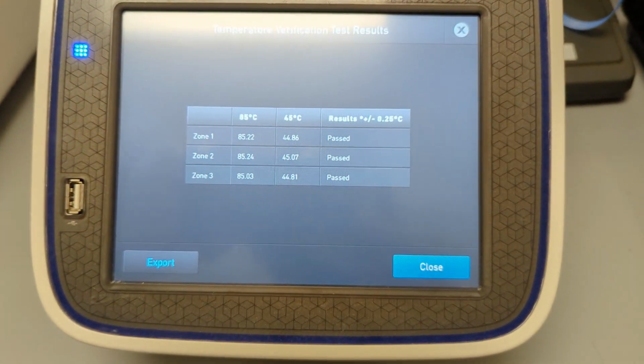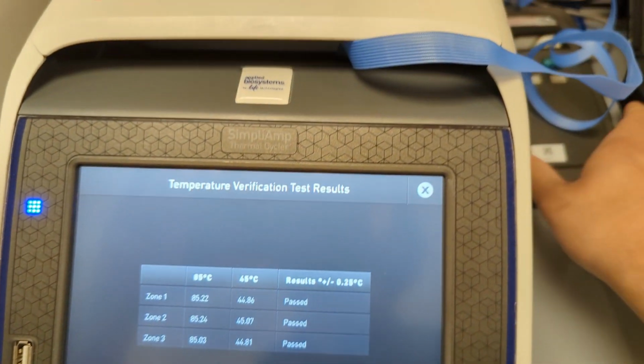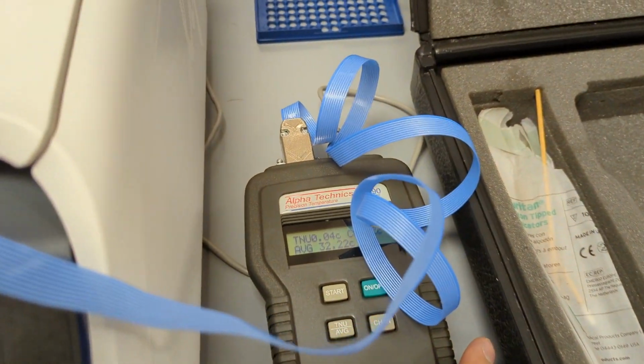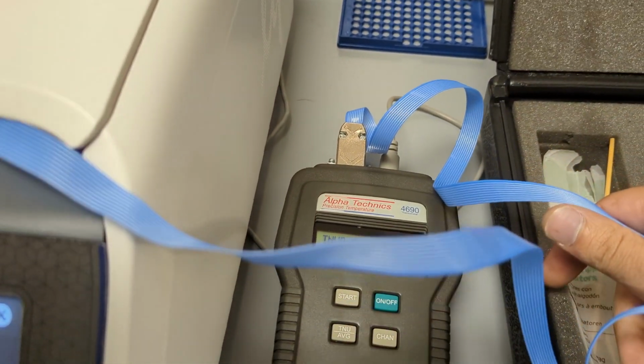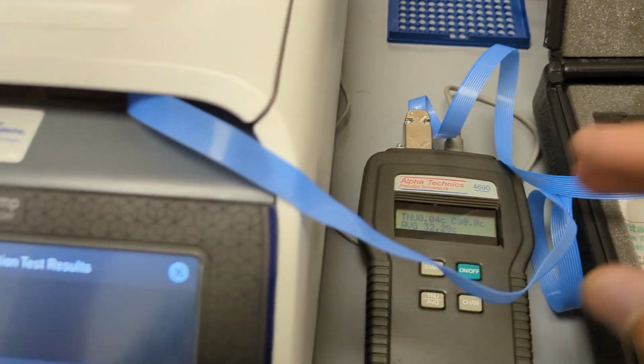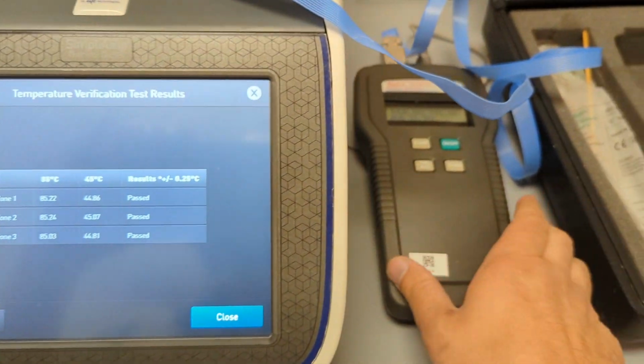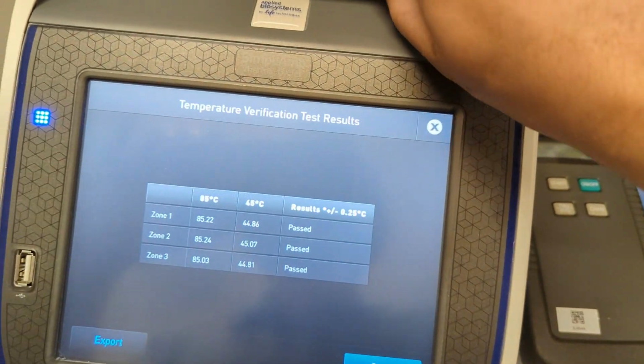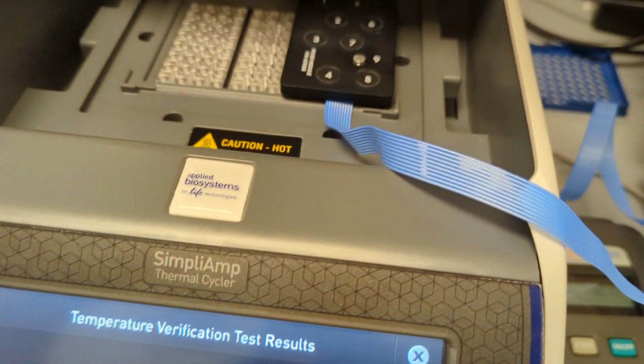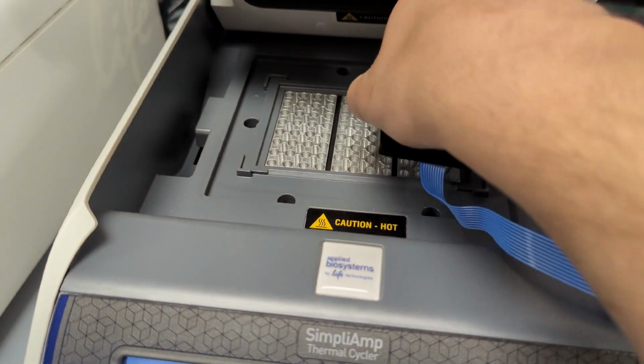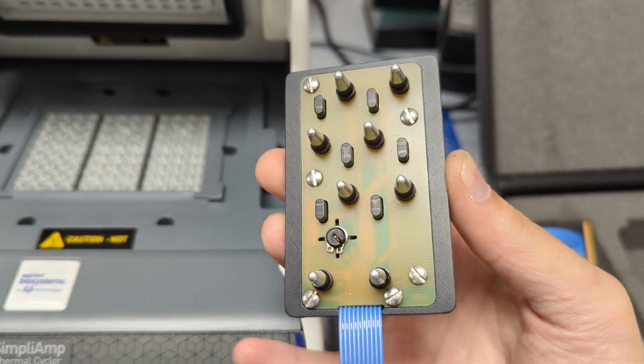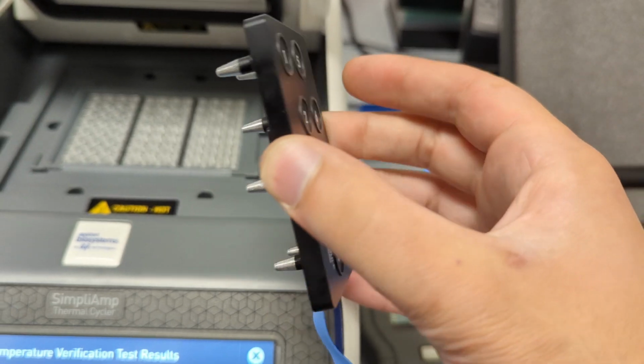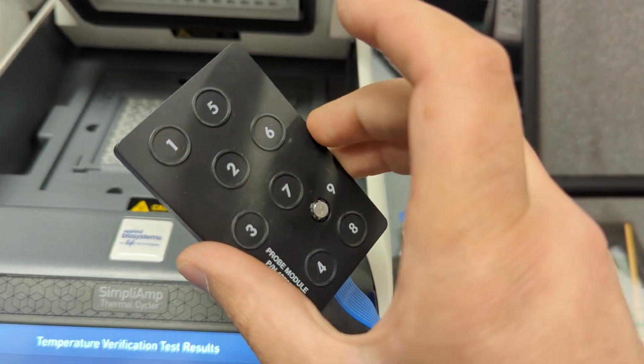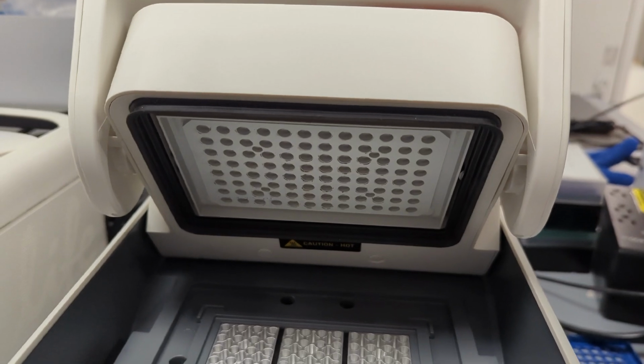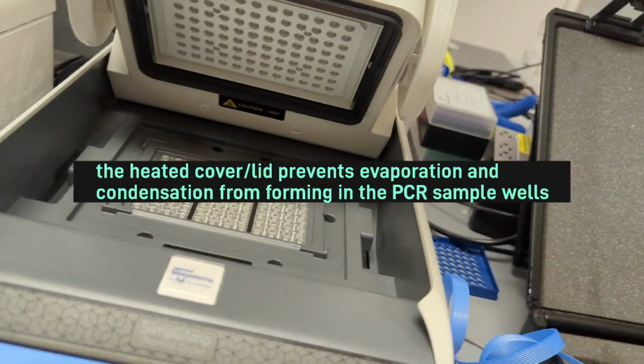Yeah, so the way that I perform these tests is using this temperature verification kit. This is a kit that you can get from ThermoFisher. They don't manufacture it, as you can see, but it is a digital thermometer with a 9-channel probe. That way you get a good reading of the block. And then of course you have a probe on the top so that it can measure the heated cover. Alright, well, we're done with that for now.